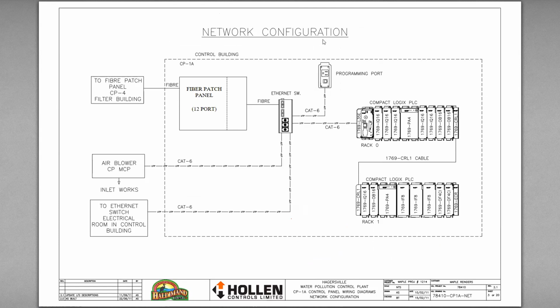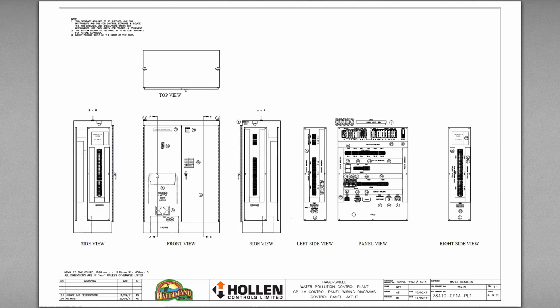Here you can see just a brief network configuration. Something like this will allow you to see, okay, we've got a Compact Logix PLC. We've got some blowers, so air blowers in the motor control panels, and then additional Ethernet switches. So if you found this, you would know quickly that VFDs were connected to the panel. Probably going to communicate with them.